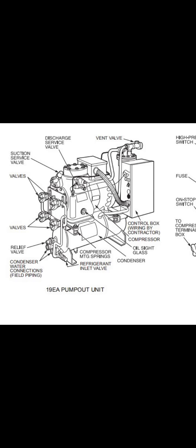So the first lesson for a centrifugal chiller, or any chiller with a large quantity of refrigerant: if you pump down or pump out, you should continuously circulate water in the chill water tubes and condenser water tubes. Do not start pump down or pump out until water circulation is established. If water circulation is not established, don't start. This is the first lesson for the centrifugal chiller.